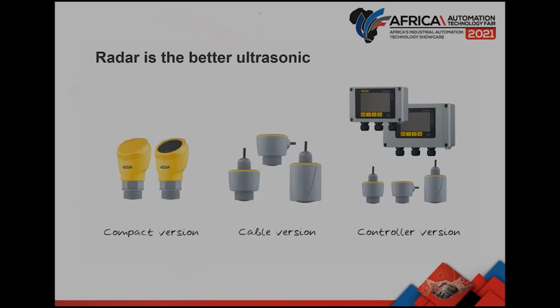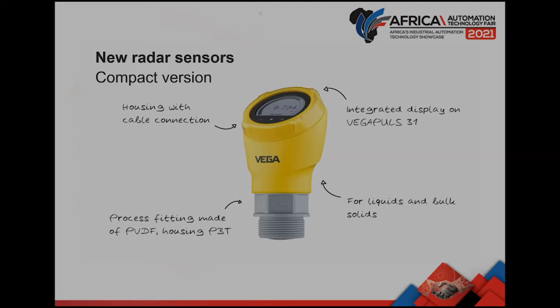So a closer view of the compact radar level transmitter. Here we can see it's a compact device with a local display as an option. This is a particular model, the VEGAPULS 31. Comes with a display. The body or the wetted parts is made of PVDF, the housing of PBT Velox plastic, which is highly UV resistant. So integrated display, as I mentioned, and this can be set up for liquids or solids measurement where we don't need the high-end devices anymore.